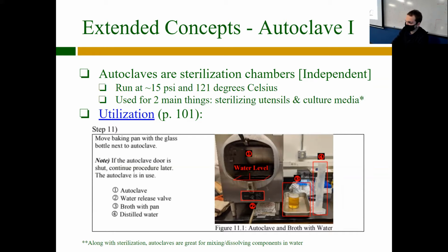Autoclaves, because they're sterilization chambers, run at around 15 psi at 121 degrees Celsius. The one we have is a little off in that regard—sometimes the temperature goes too high or too low, and specifically the pressure gauge is a little off when you're taking your materials out. It doesn't go down to 0 all the way, so if it's right around 2 or 3, just know that it's empty—there's no pressure or very little pressure inside. That's due to the winding of the gauge being a bit off.